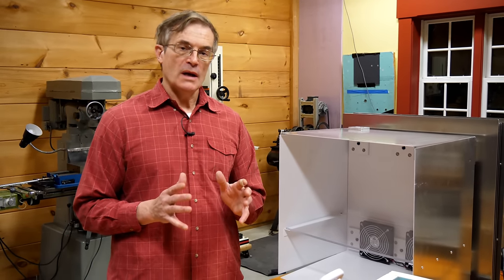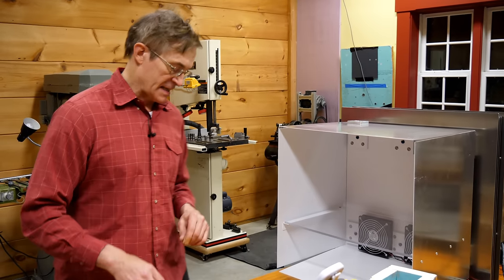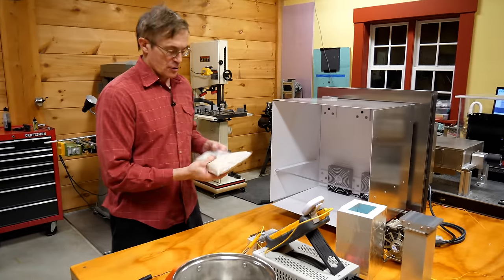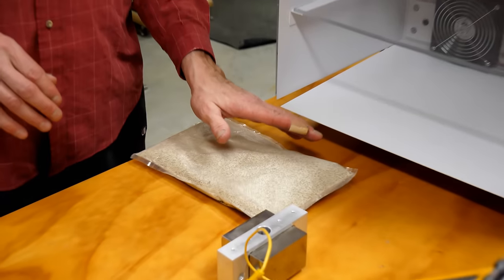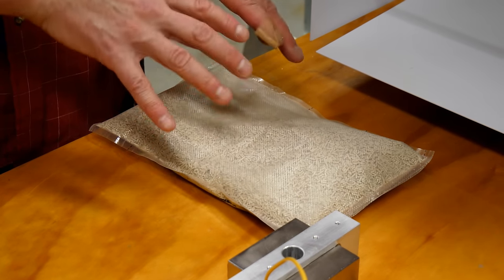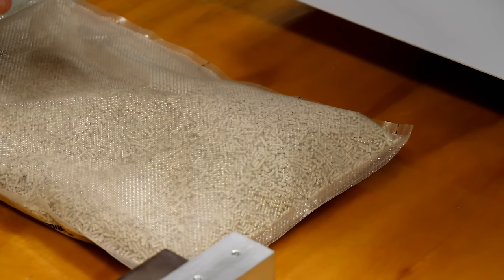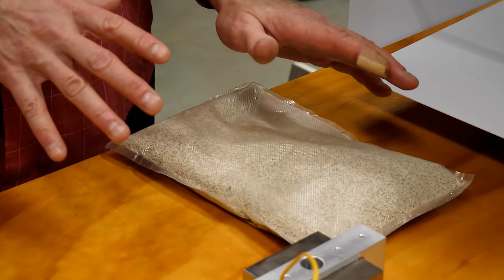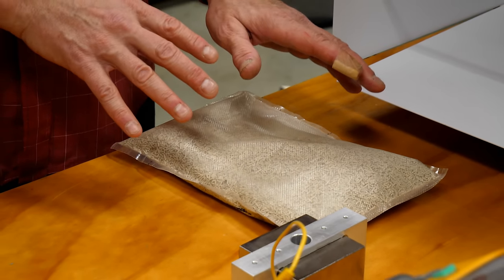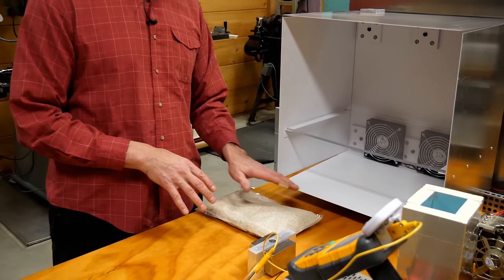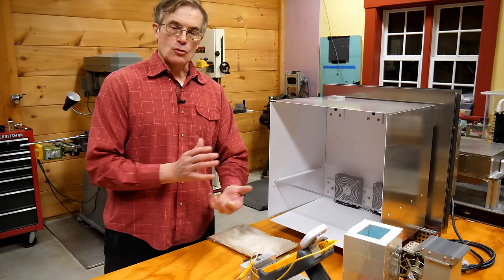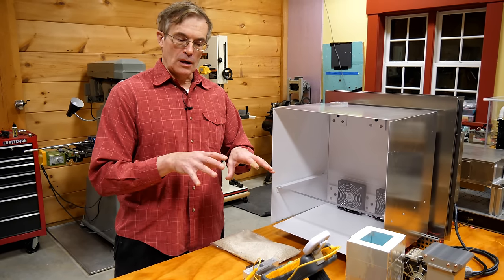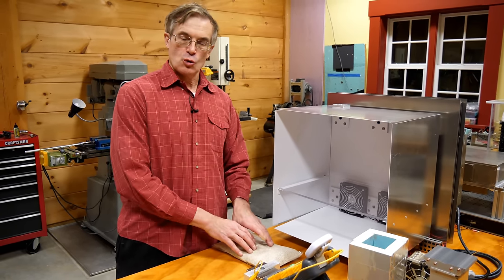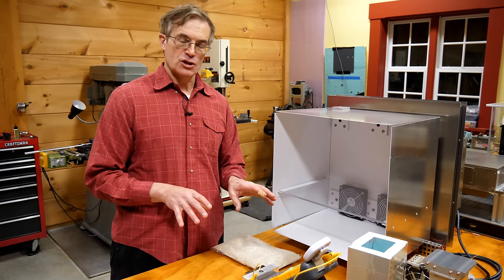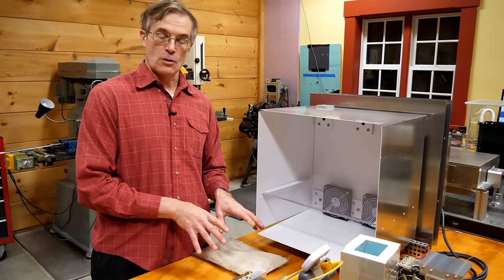But if you're not, and you don't want to add additional humidity, there's another interesting take on that. If you take a material like this, which is a desiccant, it's based on a molecular sieve and has a high absorption coefficient for water, and you heat it either electrically or with combustion or with concentrated solar, you can drive off the absorbed moisture. If you then allow the desiccant to cool back down to room temperature while in contact with a heat sink, passing air, room air, over this desiccant will allow the water in the air to be absorbed into the desiccant, and even though the air temperature doesn't really change, the relative humidity drops down near zero.